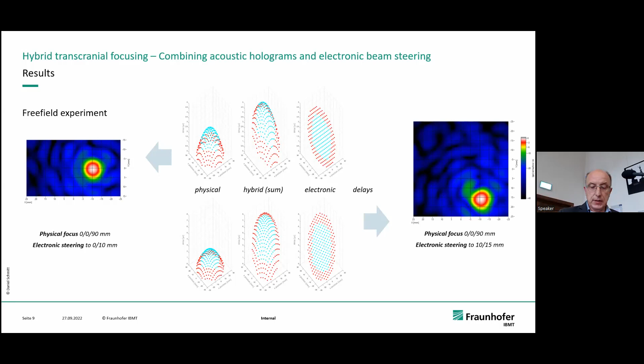If you look a bit into detail at what's happening here, you see again the situation with the focus tilted in one direction only. I plotted here the associated delay patterns. What you see here is X and Y direction and time delay in microseconds. This is the hybrid, the sum delay I require. I decompose that into a physical delay pattern, which is encoded in the mask, so this is static. On top of that, I have this tilted in two dimensions. It's a plane, actually, a tilted plane, the electronic delays. And if you think now, what am I doing when I go to another focus spot here? I'm simply tilting that plane. That is, of course, one of the advantages: it's much easier to implement into low budget hardware, for example, than a full-featured electronic focusing.